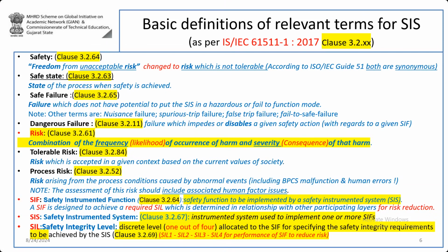It is just like a control valve. You say that you want to put a control valve and it will be a regulating type of control valve, but you do not specify the CV of the control valve, the flow coefficient. If you don't specify the CV and you say you have specified the control valve, it's a wrong specification. It's an inadequate specification. So CV is a part of the control valve specification, and SIL is a part of the SIF specification. I hope it is clear.